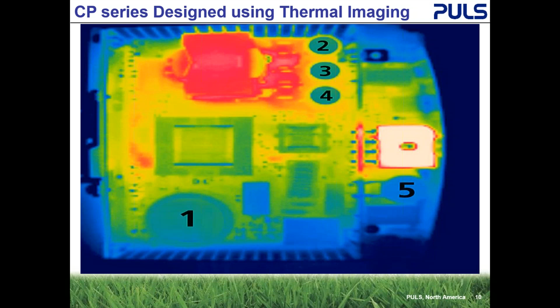And this is available if you look at the second up from the bottom, UL, you see on the very right, UL 508. That's going away for power supplies. The new UL standard is 61010-2-201, which has more to do, I'll go back a screen, to this above number one, this window pane object, the transformer. In the past, power supplies were linear 50, 60 years ago, when 508 came out and UL said, well, it's a power transformer, so that's UL 508. So the linears had a transformer and an H bridge on them, and you would adjust the transformer connections to your input voltage. Now, as you can see, the size of the transformer is greatly reduced, and it operates more now because of the microprocessors as a computer. So 61010 is not for power transformers anymore, but that's the new UL standard for power supplies.